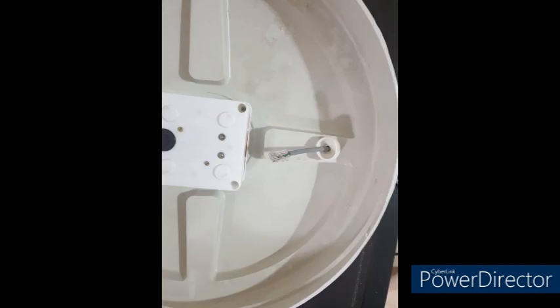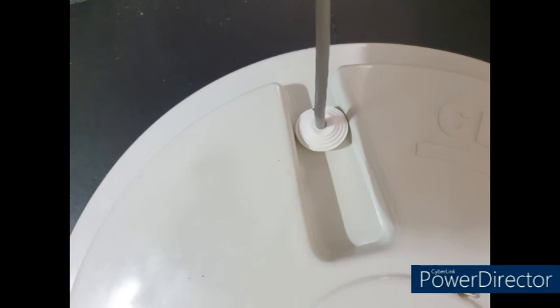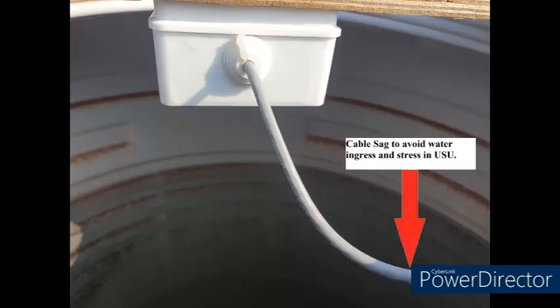The cable end with 1 grommet is passed from the cable pass hole and connected to the RJ45 socket inside the USU, while another rubber grommet remains above the lid. 1 rubber grommet is used to plug the USU hole and another rubber grommet is used to plug the cable pass hole on the lid, as shown. A small sag or loop must be left on the cable inside the tank to avoid water ingress and stress to USU, as shown in the picture.